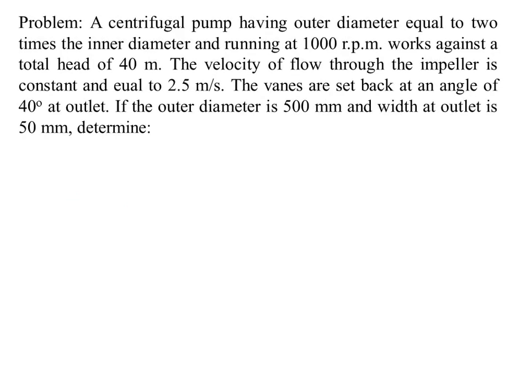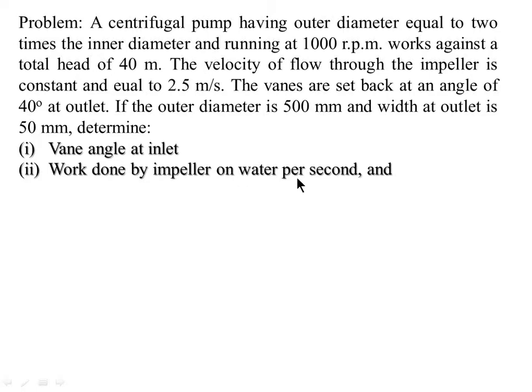The problem is: a centrifugal pump having outer diameter equal to 2 times the inner diameter, running at 1000 rpm, works against a total head of 40 meter. The velocity of flow through the impeller is constant and equal to 2.5 meter per second. The vanes are set back at an angle of 40 degree at outlet. If the outer diameter is 500 mm and width at outlet is 50 mm, determine vane angle at inlet, work done by impeller on water per second, and manometric efficiency.